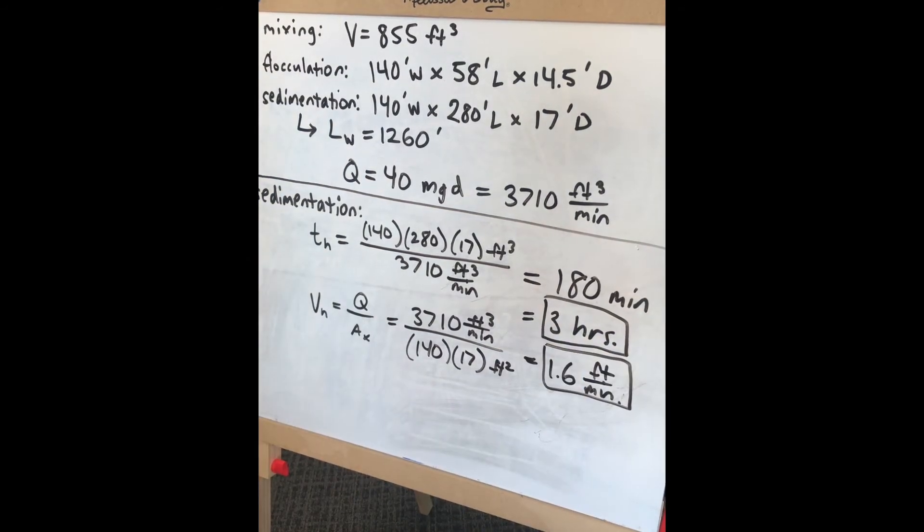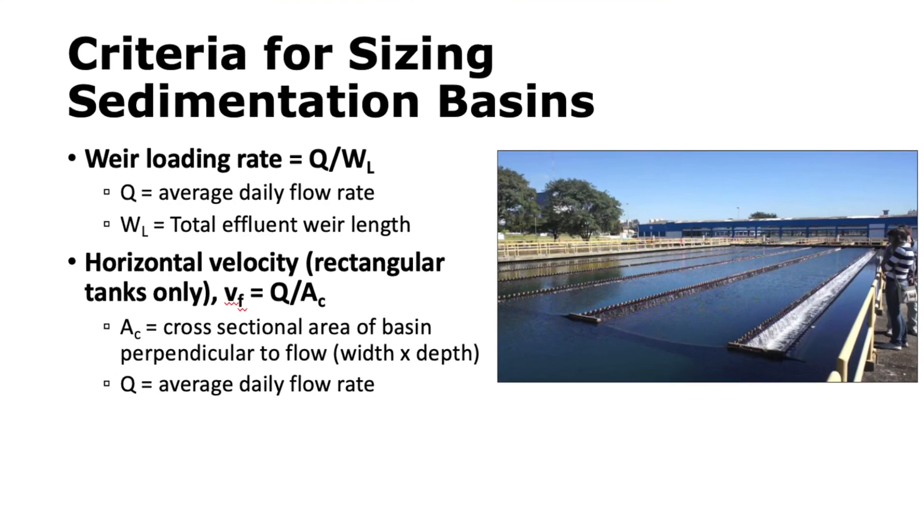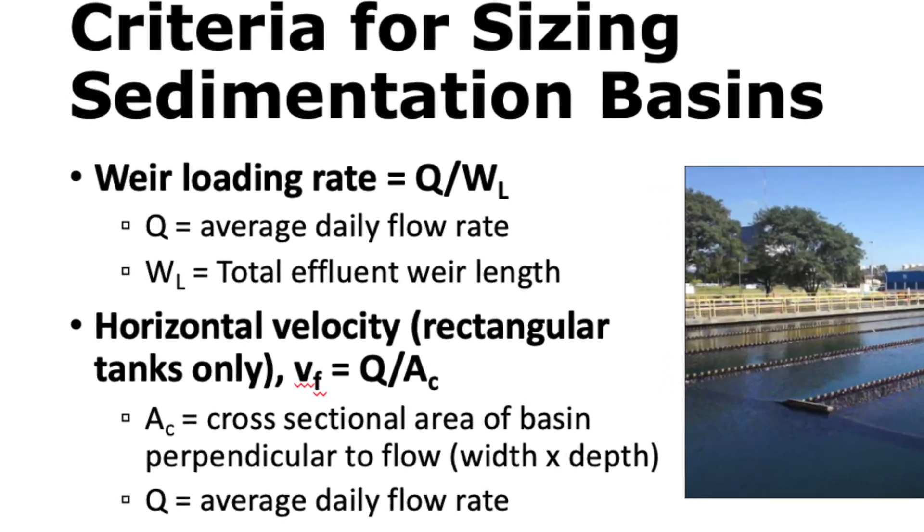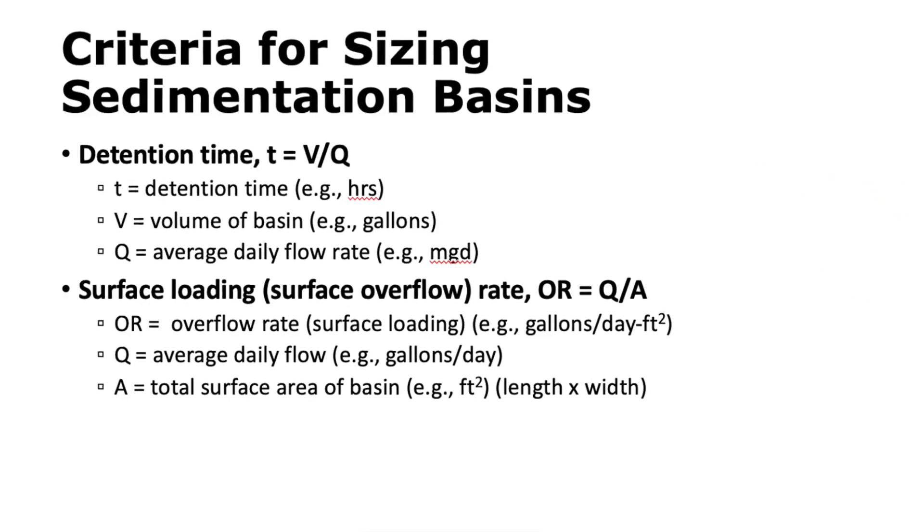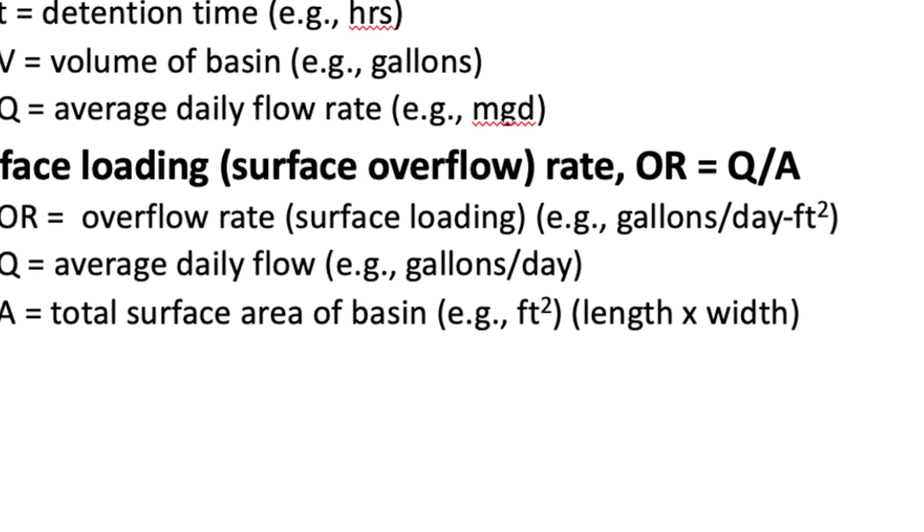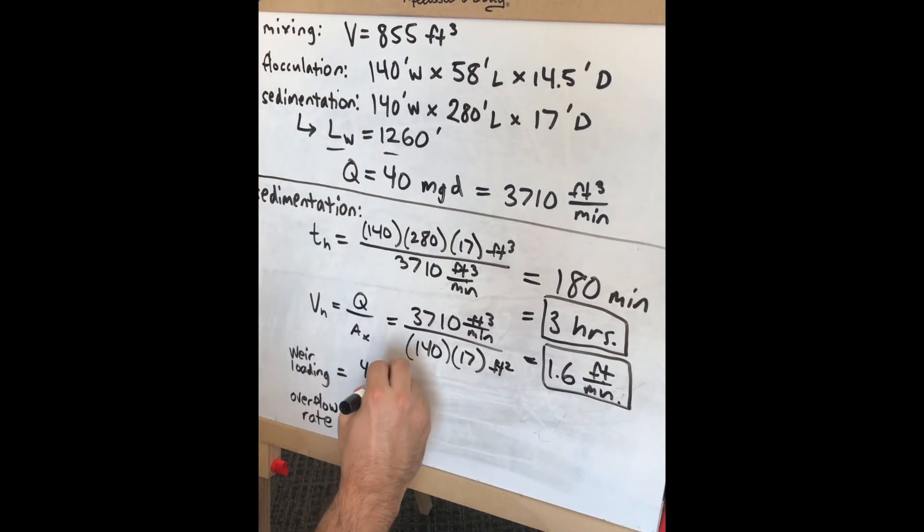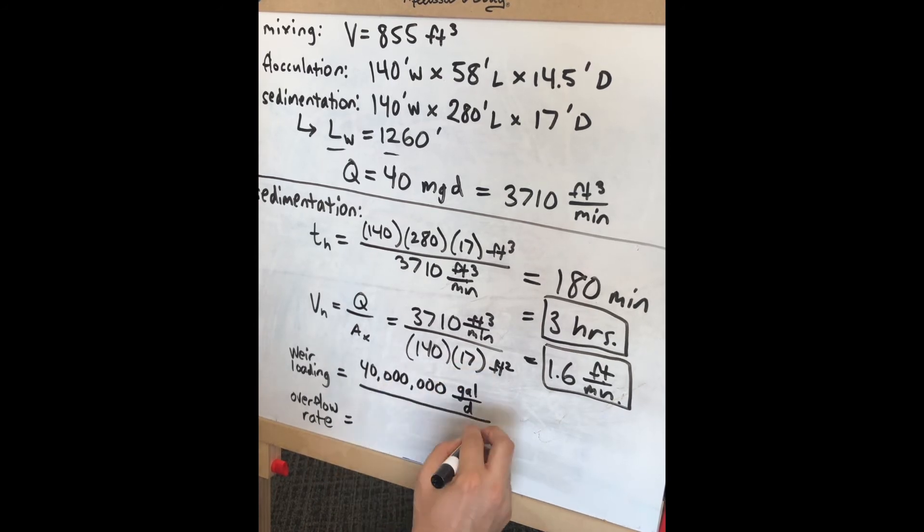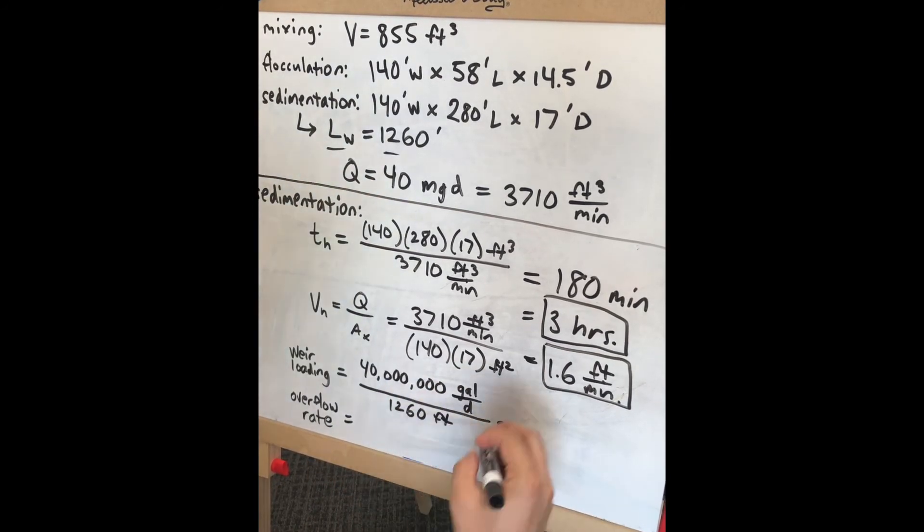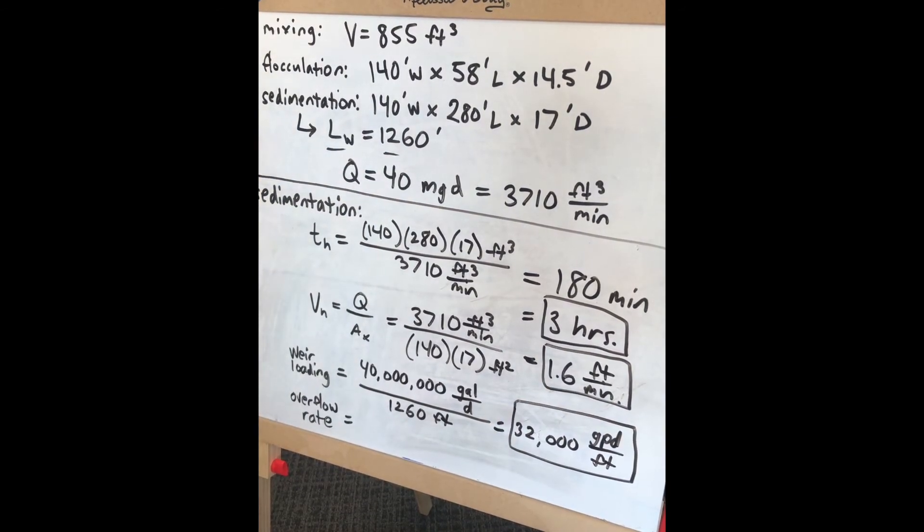For sedimentation basins, we also calculate two additional parameters: weir loading rate and overflow rate. The weir loading rate equals the flow rate divided by the weir length, giving 32,000 gallons per day per foot.